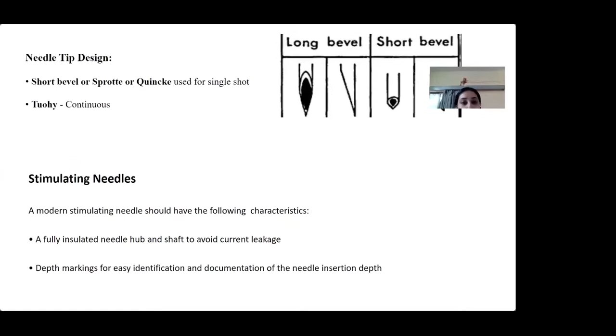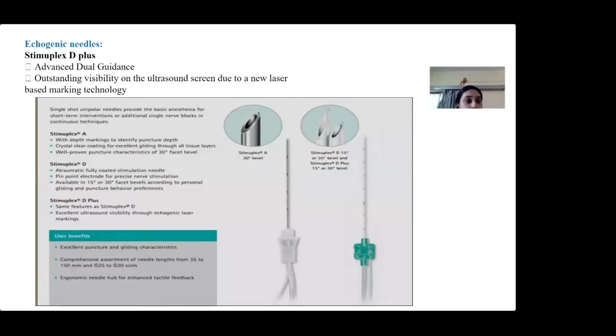Now the stimulating needles should be fully insulated. They should have a fully insulated needle hub and shaft to avoid any current leakage. And depth markings should be there for easy identification and documentation of the needle depth. As you can see here, these are the imaging needles used while using both a peripheral nerve stimulator and ultrasound.